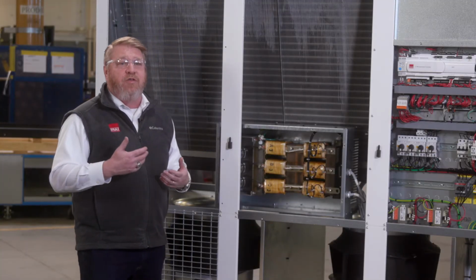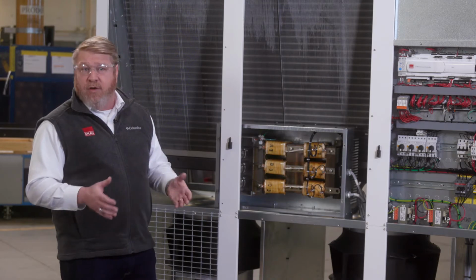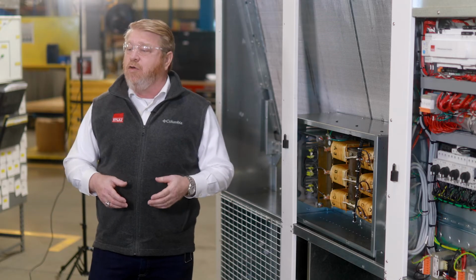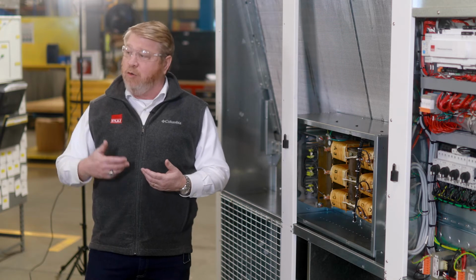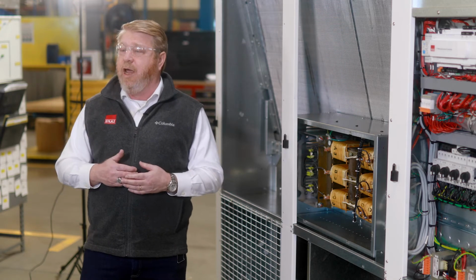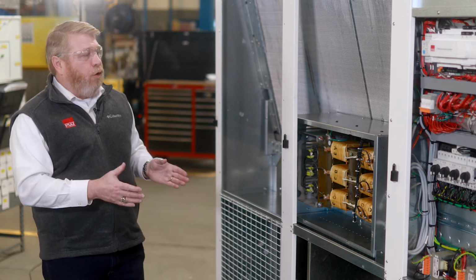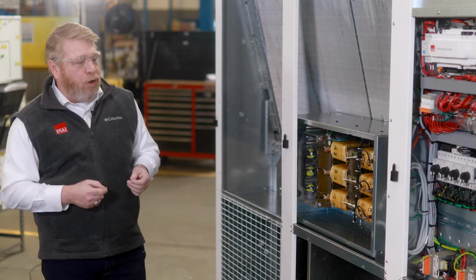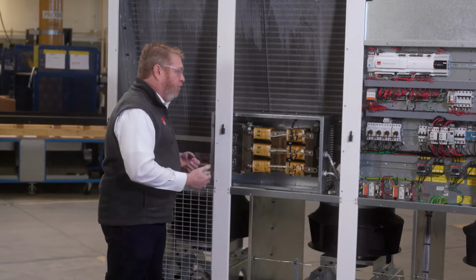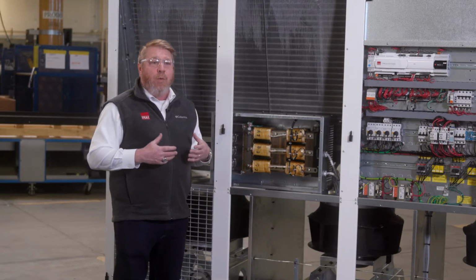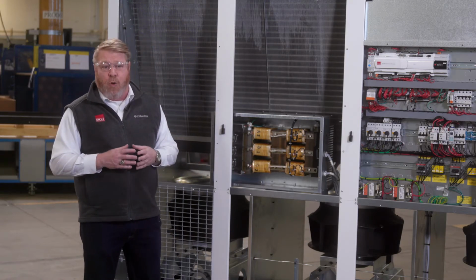So the most common way to vary the speed of a piece of mechanical equipment, whether it be a fan or a pump, is either to use an electronically commutated motor, which is probably the most common fan motor in the data center today, or possibly using a VFD for a fan or a pump. And the difference is simply how these components go about varying the speed of the mechanical device. Now, since we're able to control the speed of the device and match the load within the space, that is a positive. The negative, of course, is the fact that we develop what is known as total harmonic distortion.